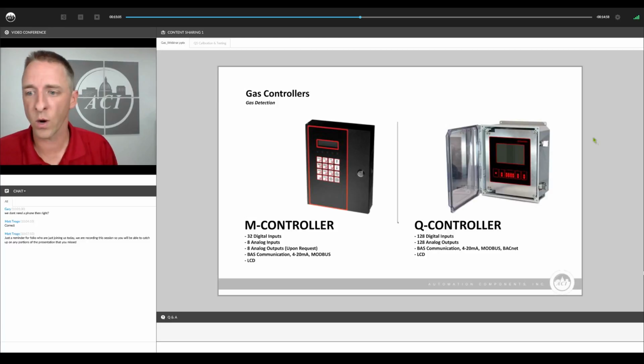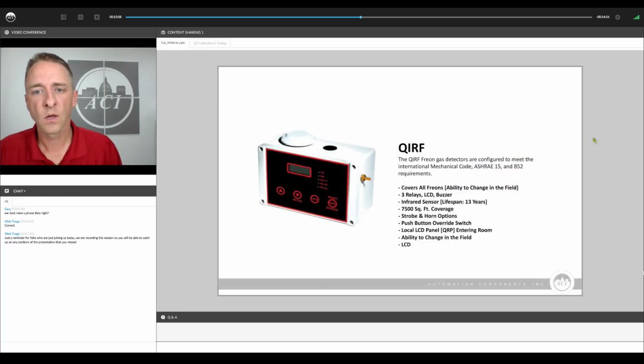We also have an infrared freon monitor for refrigerant leak detection. This again is a completely standalone system that can monitor all types of freons. It can be field programmed, so our distributor partners can have one version in stock, and then it can be programmed to detect all of the different types of freons that you may come across in the field. It's got an integral horn and strobe, and it also can use relays that are packaged on the board to sound an external strobe or alarm outside of the space where the refrigerant leak may be.